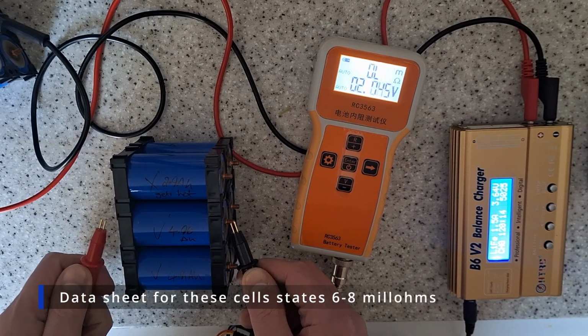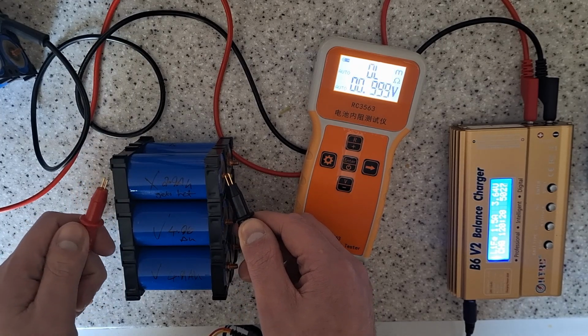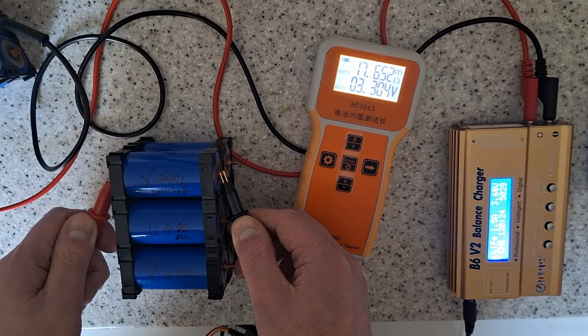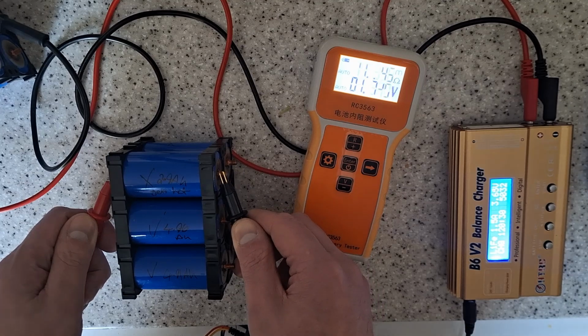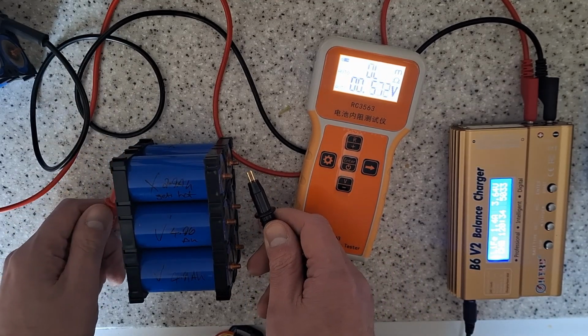It's about 7 ohms - 7 milliohms, 7.04. That's a known good one. 7.05, and then this is a bad one - 17 milliohms. We don't even need to test that any further; we know that's a bad cell. It needs to be about 7 milliohms to be good.